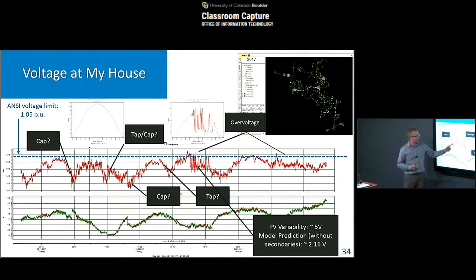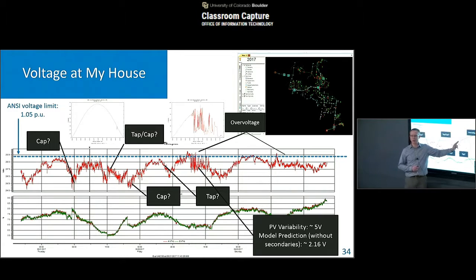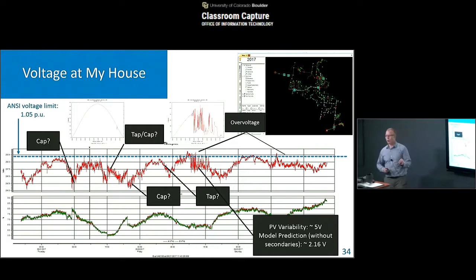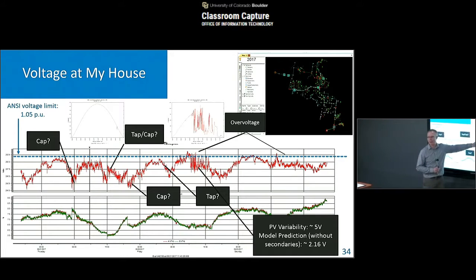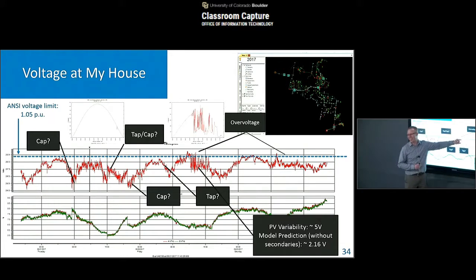The system, as it operates now, does a pretty good job keeping voltage within its bands. So these are actual measurements from my house. And you can see when they take corrective actions. Do they use a capacitor bank? Do they do a tap changer? Things like that. When you get a lot of PV variability, Xcel's already going outside of those limits. Now, that has big implications. So, as an example, I think this is why the cap bank on my AC unit blew. Because of this, exactly. And that's why I started looking into this.